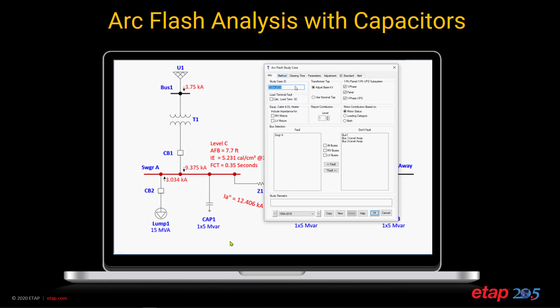You can also calculate the capacitor thermal energy with the network calculation within ETAP arc flash analysis. In this sample, an arc fault is placed on switchgear A, and when the arc flash event takes place, the capacitor's energy is expected to dissipate quickly due to the relatively small resistance of the arc. Examining the fault location, we identify three contributions: from the source, the load, and the capacitor bank. In most cases, the capacitor thermal energy is relatively small compared to the energy from the actual voltage sources; however, there are exceptions, such as large capacitor banks, which can store a significant amount of energy.